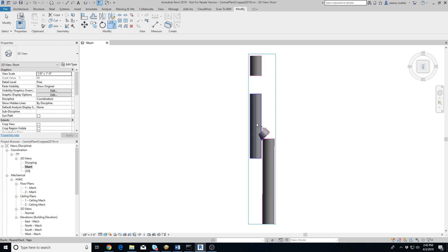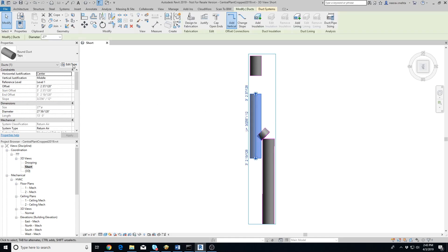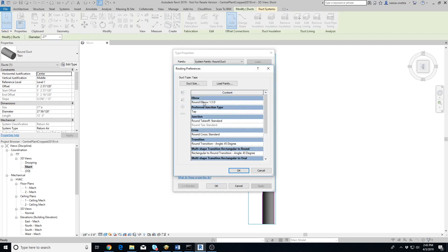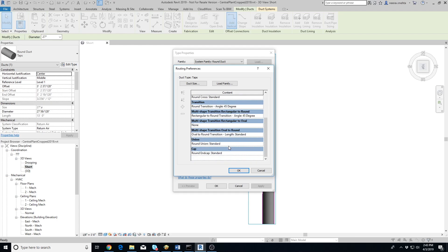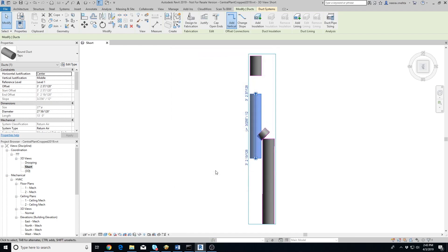To connect the two extracted ducts, we'll need to use the Align and Connect button provided in our add-in. But before that, you need to make sure that the duct elbows and transitions are already loaded. You can verify that by selecting a duct, clicking on Edit Type, editing routing preferences and making sure that elbow and transition fittings are defined. If not, you'll first need to load the appropriate families in Revit and configure them in duct types routing preferences.